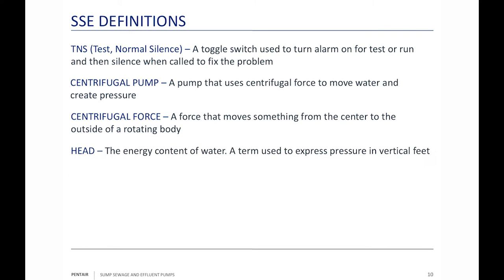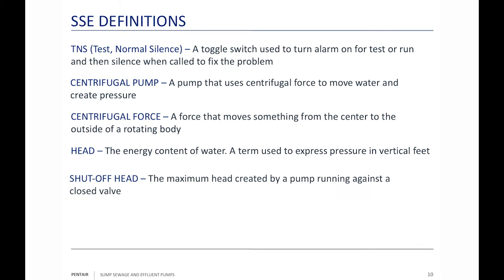Head is our term for the energy content of the water. Especially in SSE, head is considered a vertical lift — a vertical column. How high is that vertical column of water? That's the amount of head the pump can produce. Shut-off head calculates the maximum head a pump can produce, measured here in the factory with clean water, since dirty water would plug the pressure gauge.